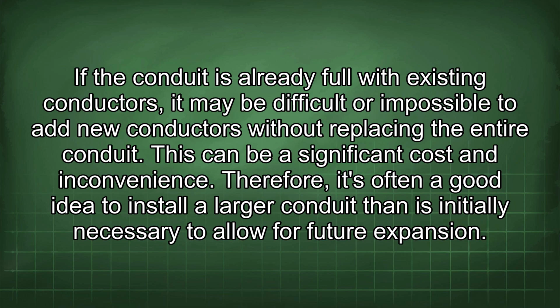If the conduit is already full with existing conductors, it may be difficult or impossible to add new conductors without replacing the entire conduit. This can be a significant cost and inconvenience. Therefore, it's often a good idea to install a larger conduit than is initially necessary to allow for future expansion.